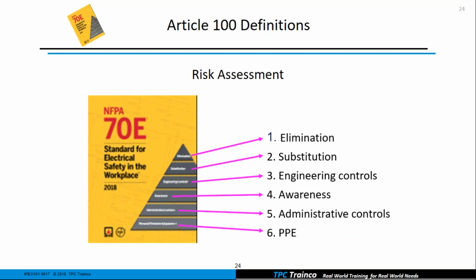And then our last form of controlling these hazards is our personal protective equipment. So remember, the NFPA gives you these choices 1 through 6, and look, their last choice on how to keep a worker safe is personal protective equipment. And too many times out in the field, that might be a person's first choice, that they're going to put that on first. Well, that's really not what OSHA and the NFPA want to see. They'd like to see us try to utilize those top 5 before we ever get to number 6.